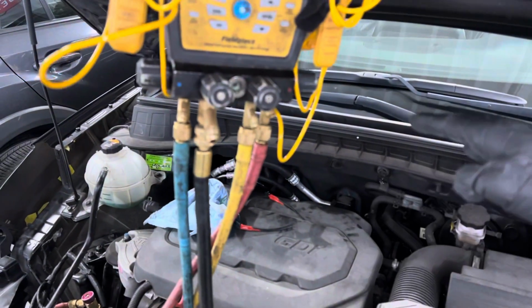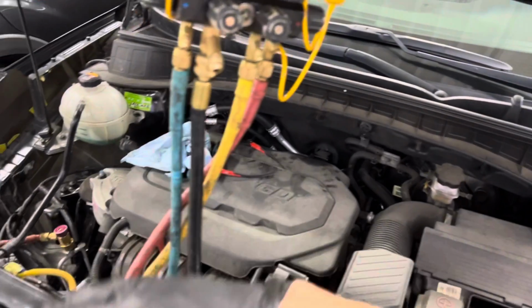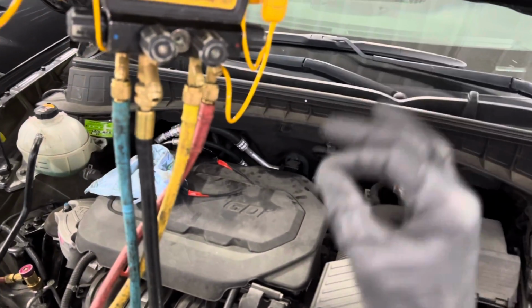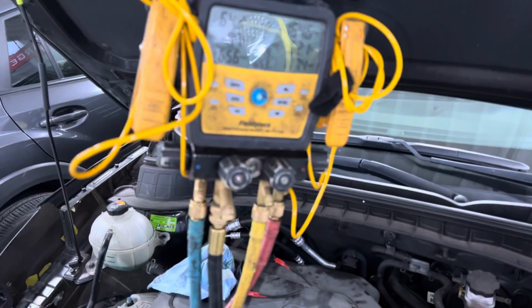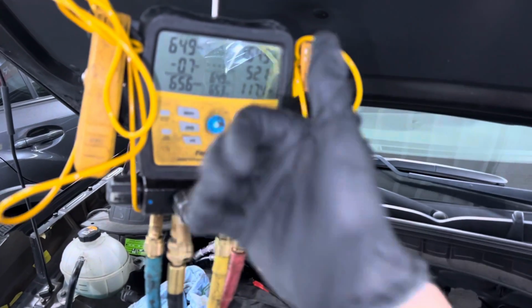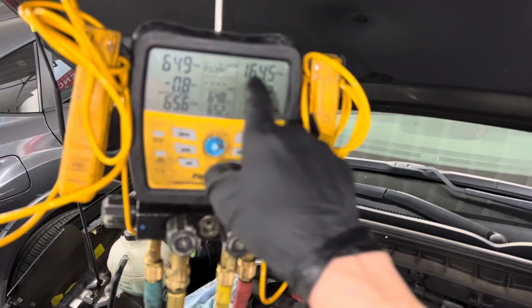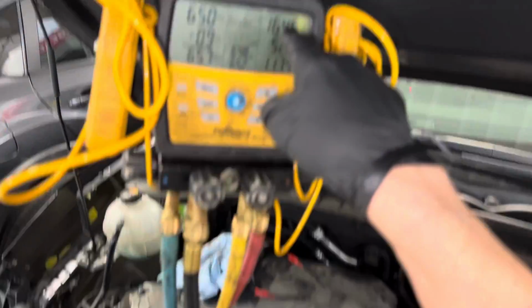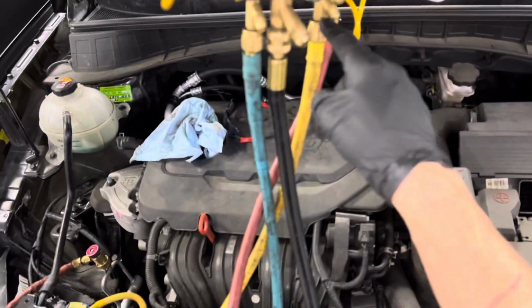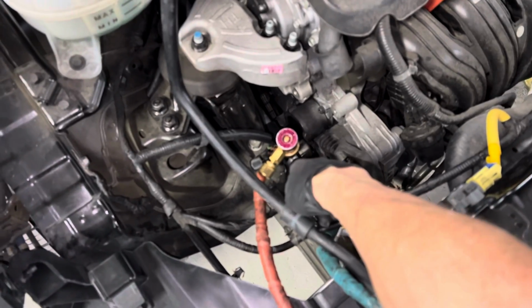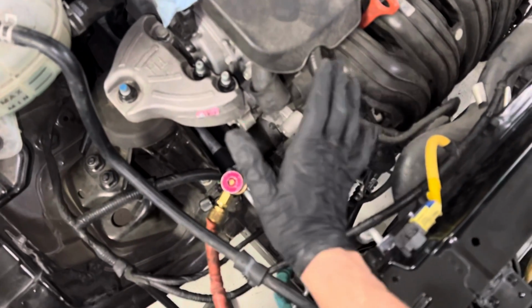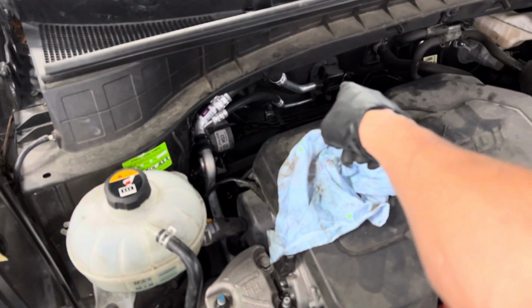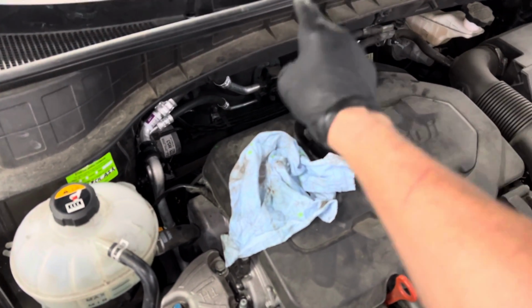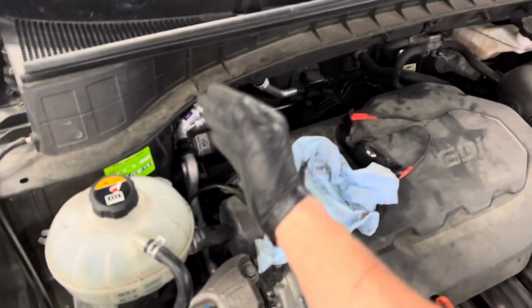A lot of you guys got to study this. I'm not going to explain it in detail right now, but they like to leave a differential in pressure from your high side to a low side. Some manufacturers, some things, that's usually some, I'm not going to say all, and I'm not going to say everyone. There's kind of rules of thumb, and in this case it's exactly 100 psi. I'm pumping in high side nitrogen right from the high side nitrogen tank, and it's only down the high side. I pump this up with 164 psi. It cannot go backwards through the compressor, and because of the spring action and the diaphragm action, the way the expansion valve is, it keeps 100 psi differential pressure from the low side to the high side.